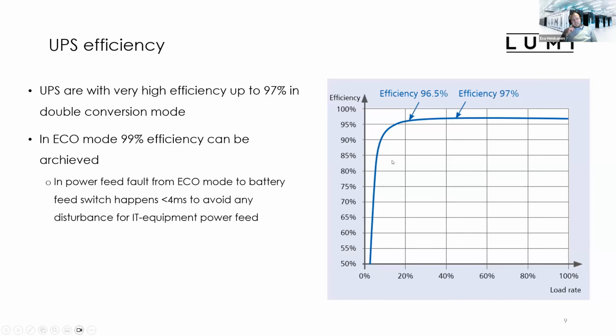A little bit about UPS efficiency. In the procurement, we set pretty high requirements for the energy efficiency of the UPS system. In our case, we have at most 50% of the UPS load rated in normal operation, because we have 2 separate power feeds taking all the cabinets from 2 different UPSs, and in case of a power feed failure, one UPS should be able to provide full capacity to all the air-cooled cabinets. We are operating at a 50% load rate at maximum, but already there, the UPS efficiency is up to 97%.